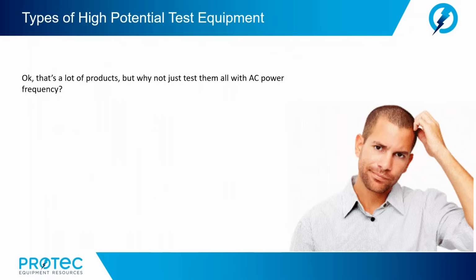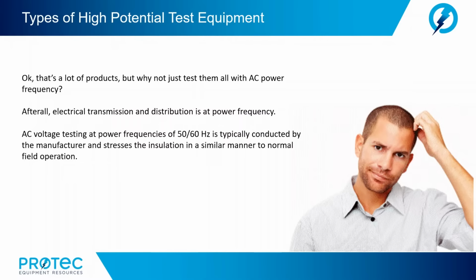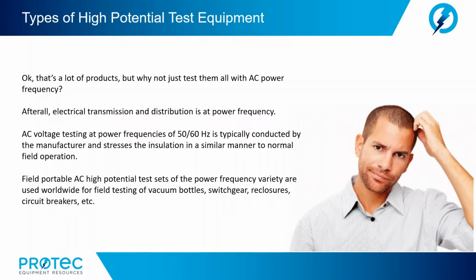All right, that is a lot of products that we just listed, but why not just test them all at AC power frequency, right? I mean, after all, electrical transmission and distribution is at power frequencies, 50, 60 hertz. Now, AC voltage testing at power frequencies, 50, 60 hertz, is typically conducted by the manufacturer, and it stresses the insulation in a similar manner to normal field operation, right? Well, field portable AC high potential test sets of the power frequency variety are in fact used worldwide for field testing of vacuum bottles, switchgear, reclosures, circuit breakers, and so on.